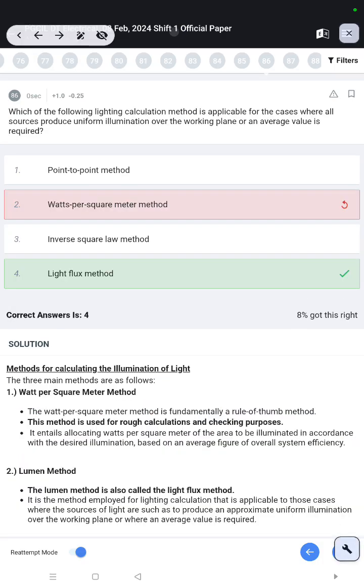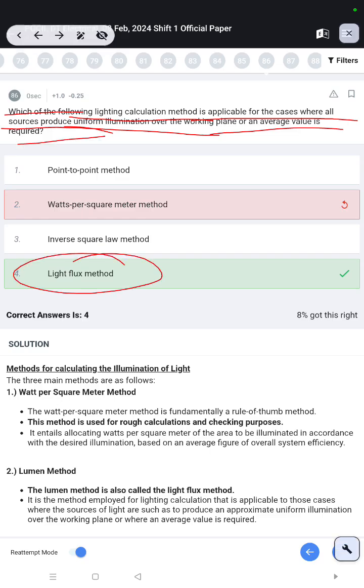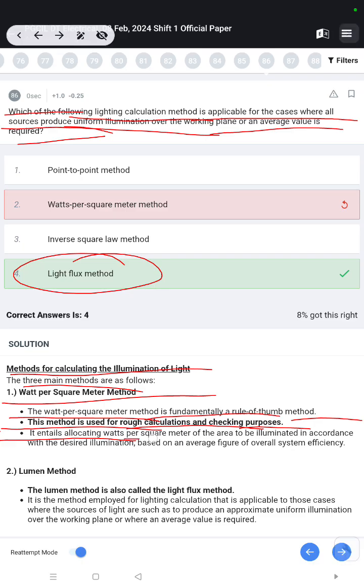Which of the following lighting calculation methods is applicable for cases where all sources produce uniform illumination over the working plane or an average value is required? Light flux method. Methods for calculating the illumination of light. The three main methods are as follows: watt per square meter method. The watt per square meter method is fundamentally a rule of thumb method. This method is used for rough calculations and checking purposes. It entails allocating watts per square meter of the area to be illuminated in accordance with the desired illumination based on the average figure of overall system efficiency.